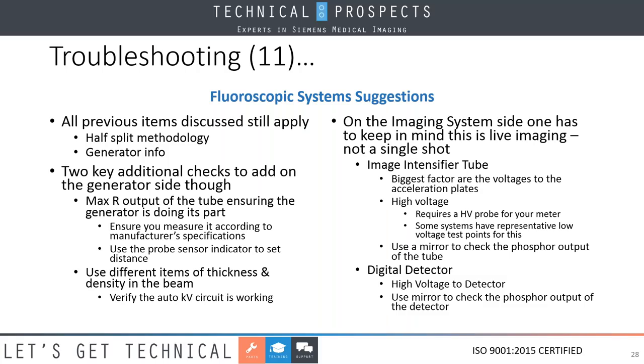The image intensifier, typically they don't go bad. Typically the biggest problem here is that the voltages to the acceleration plates are not correct. Okay. You may need a high voltage probe for this. All right. Some have low voltage systems where you can monitor it there. All right. Don't be afraid to break the circuit. Put a mirror in there. Check the output of the green off of your II. All right. Same thing with a digital detector. Monitor the output when it comes to this.